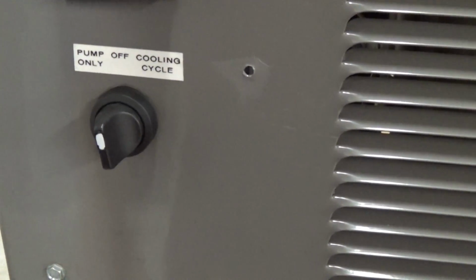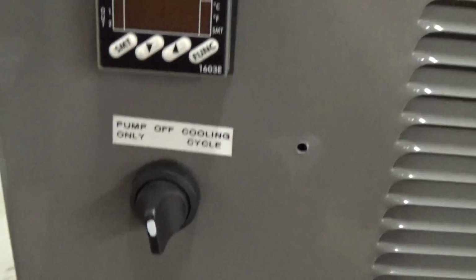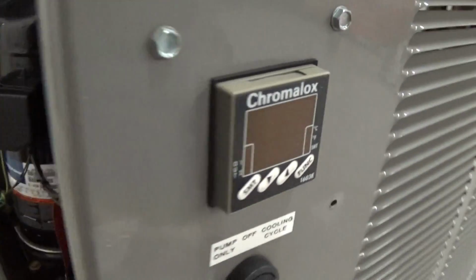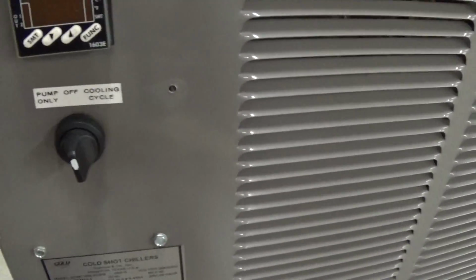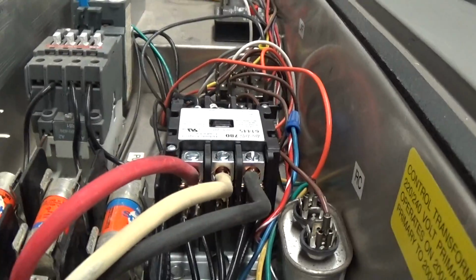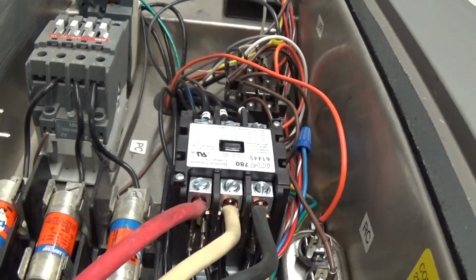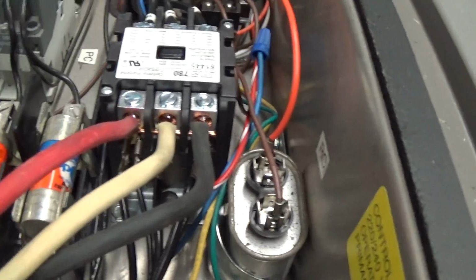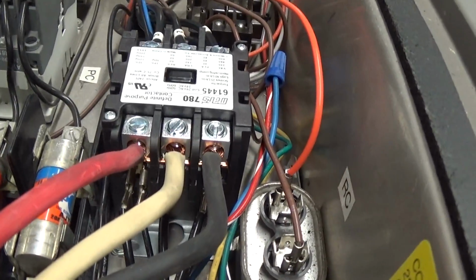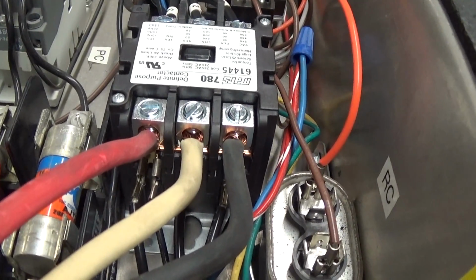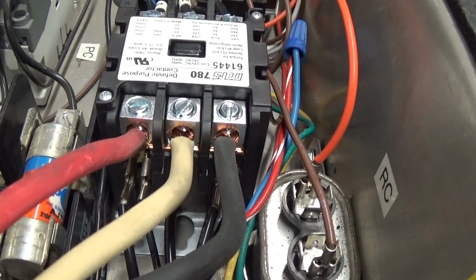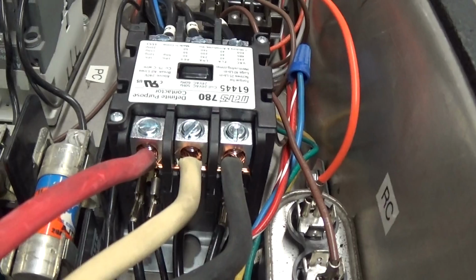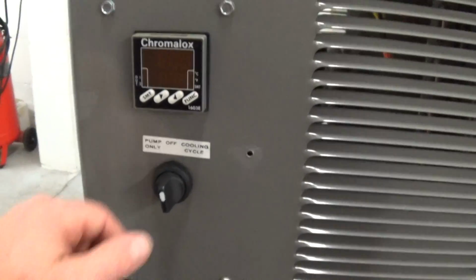back of the pump. If it's rotating in the wrong direction, then you disconnect your main power and either change any two of the leads at your receptacle plug, although you're probably not going to use a receptacle plug with this type of amps. Then you'd probably swap out any two of your L1, L2, L3 here. Then reconnect your power, double check the rotation, and you should be good to go.